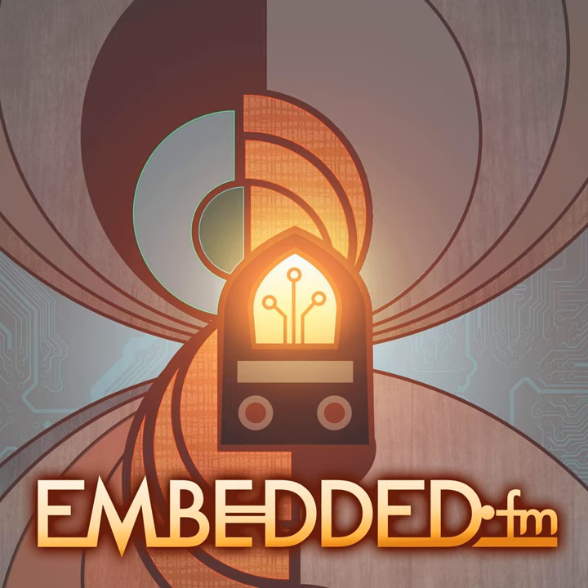There's a product I've been developing over the last 2 years called Joulescope, and that's its entire purpose. It's been very frustrating to measure these dynamic ranges of currents, where you'd typically have to put it in high power mode and measure there, then specifically set it up for low power mode and measure separately. With Joulescope, there's a variable shunt resistor that switches so fast it can go from a big shunt resistor for low currents down to a much smaller one for high currents without affecting the device you're measuring.